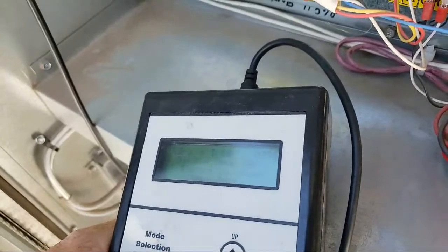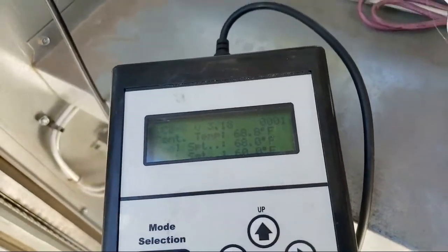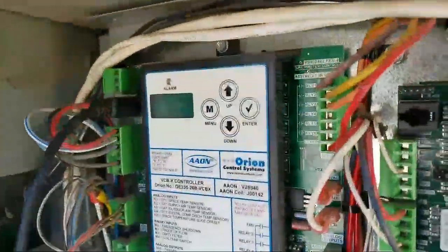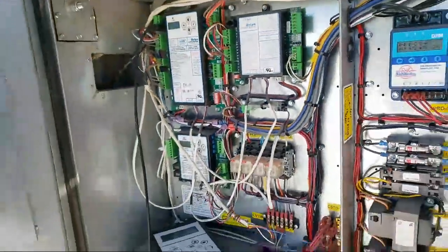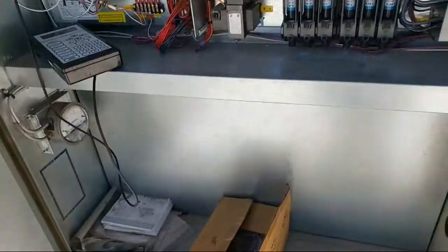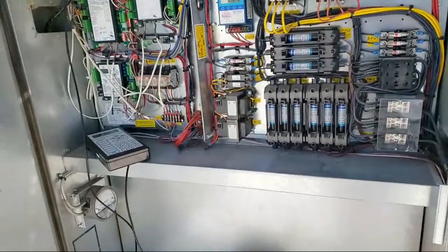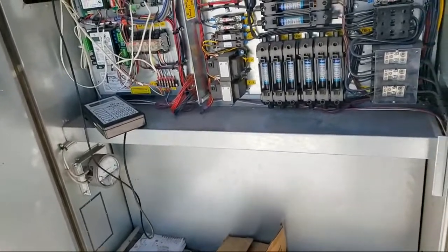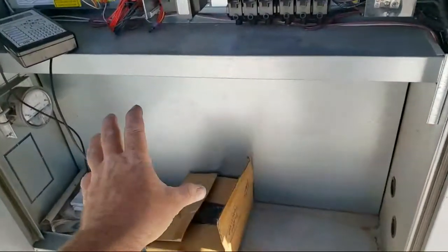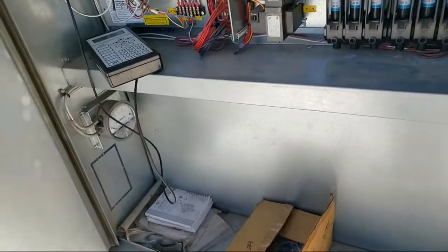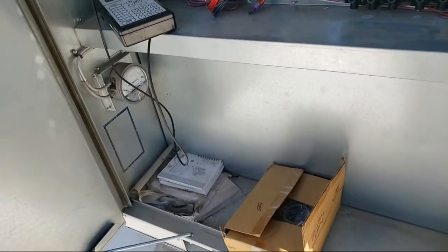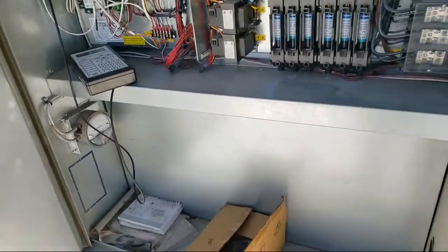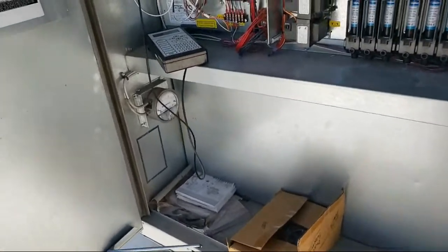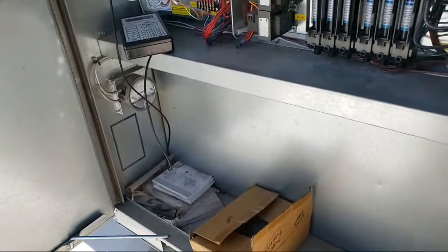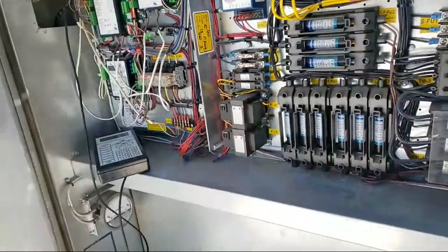Whoever set up the server room had their own vendor doing it. So, as I said, most of these units I've dealt with, if they've been in a controlled environment, if they care about the relative humidity, I usually always also have a bank of electric heat. When you're running space temperatures really cold in the 60s, like surgery rooms or other critical air. But for this critical air, it's for computer servers, and they didn't spec it with the electric reheat. It just has the one changeover valve to reheat.